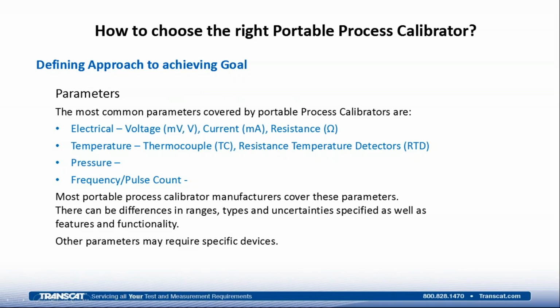So let's talk about parameters. They can be wide and varied, obviously, in any facility, process, petrochemical plant, power utility, or other industrial facility. But the most common parameters covered by portable process calibrators are electrical parameters: voltage, current, resistance, obviously temperature, so thermocouple devices, RTDs, pressure, and frequency pulse counting. Most portable process calibrator manufacturers cover most of these parameters. There are differences in the ranges, the types, and uncertainties specified, as well as features and functionalities of different calibrators. Other parameters, apart from these primary ones, may require other specific devices.